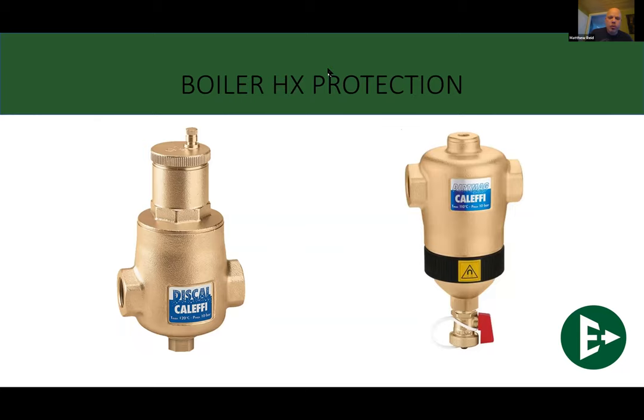What solvents do you suggest using on cleaning? Okay, so when we're talking about cleaning out a heat exchanger, Fernox makes a beautiful cleaner. But to be honest with you, friends, the best one that I come across is using pressurized steam to clean these guys. If you can find it, if you can get into it, pressurized steam is a great way to get the gunk off the inside of these heat exchangers. It's extremely good. Because it is stainless steel, there's no real bad option with regards to which one I would recommend.